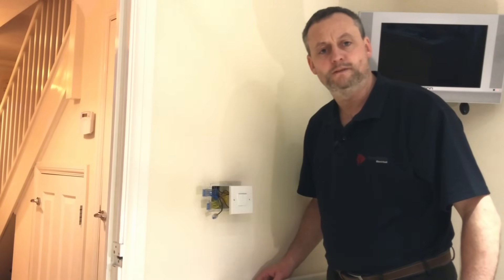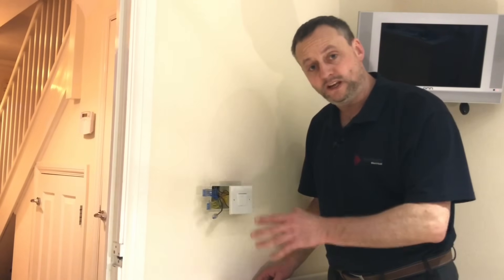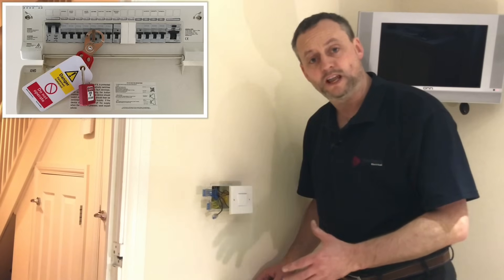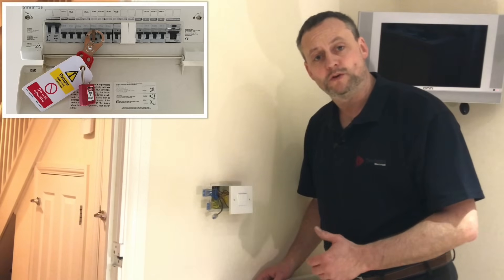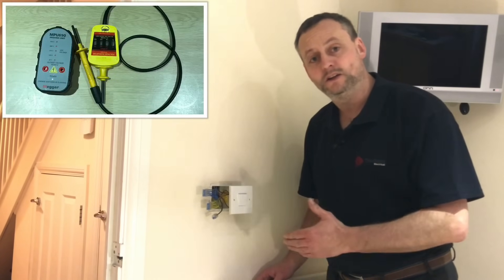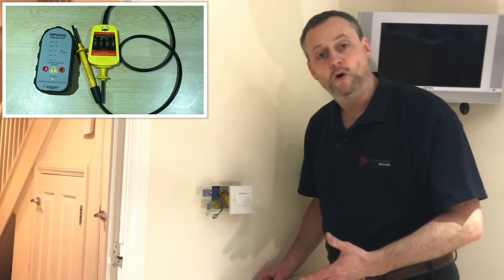We're carrying on from the previous presentation, looking at feeding the switch. I've isolated this circuit, secured isolation, and locked it off. I've used my proving unit and proved the circuit is dead. I've also seen the lights in the area go off.